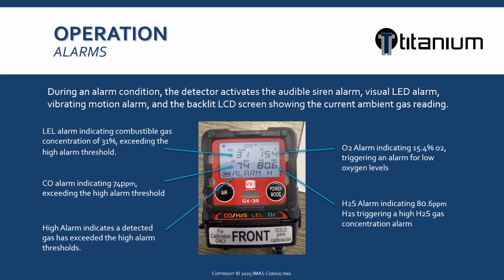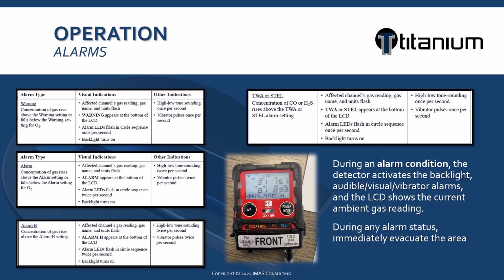During an alarm condition, the detector activates the audible siren alarm, visual LED alarm, vibrating motion alarm, and the backlit LCD screen showing the current ambient gas reading. During this alarm test, the LEL alarm indicating combustible gas concentration of 31%, the CO alarm indicating 74 ppm, and the high alarm indicates a detected gas has all exceeded the high alarm thresholds. The O2 alarm indicating 15.4% oxygen, triggering an alarm for low oxygen levels, and the H2S alarm indicating 80.6 parts per million of H2S, triggering a high H2S gas concentration alarm. During any alarm status, immediately evacuate the area.